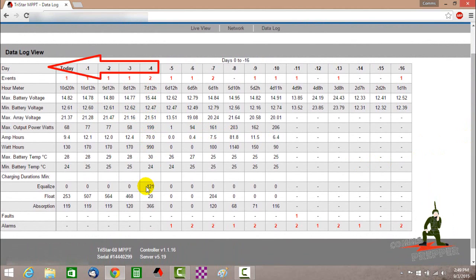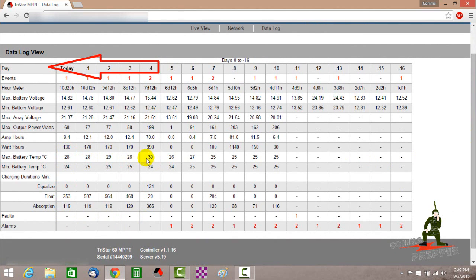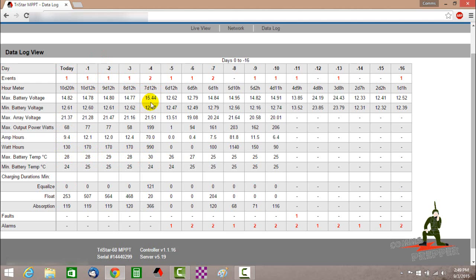So that was starting Sunday. And you can actually see here we're looking at equalization of float voltages, absorption below, battery temperature for the past five days. The max battery voltage and here I'm showing the 15.4 volts that was equalization that we performed last Sunday. And then the typical absorption rate during the day of 14.8 volts. So this allows you to see what your charge controller is up to.